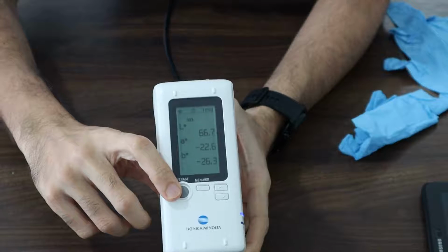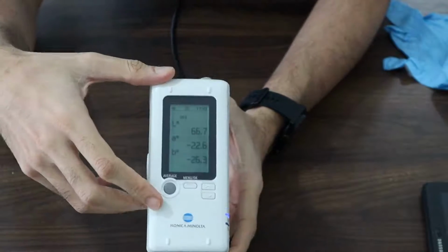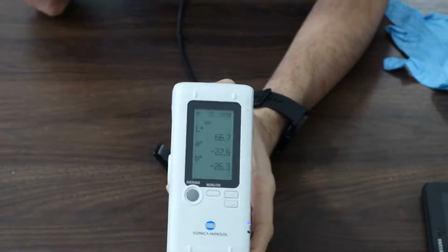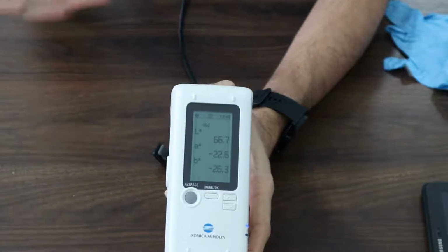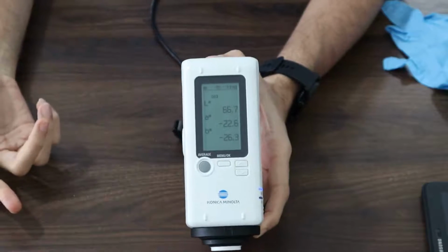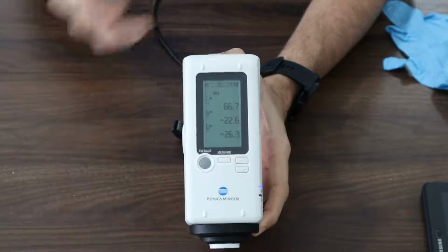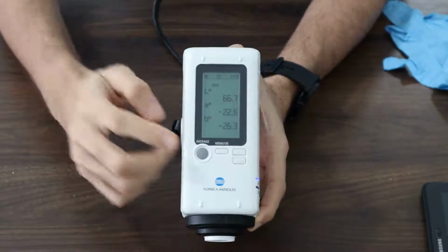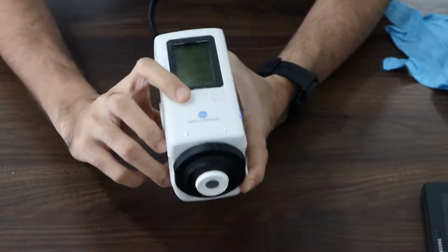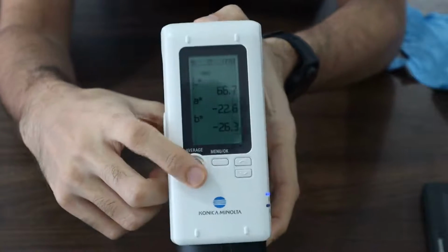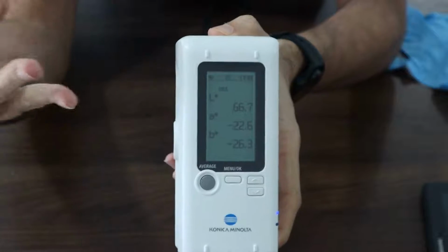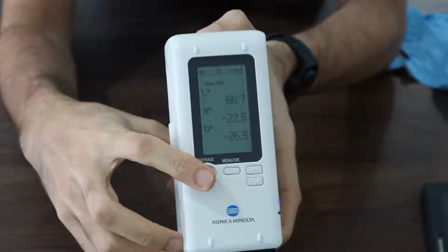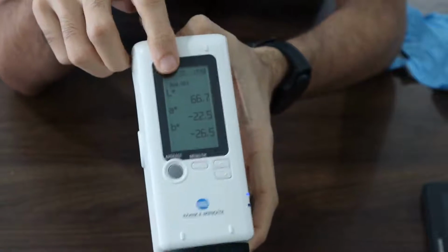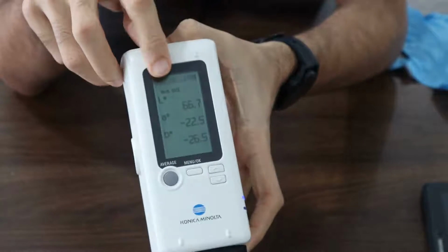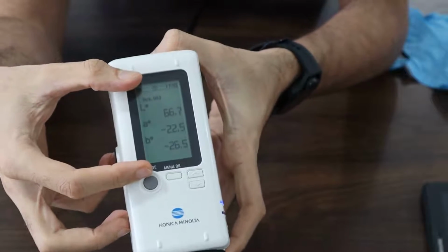This button is an average function button. The purpose of it is that instead of measuring 5 different samples and manually calculating the average, the equipment is able to measure 5 separate measurements, and by pressing average now, currently if you see here it's written 003. So when I click average, it will be the average of the last 3 measurements that I've made. So when I click average, I will get another measurement says AVG 003, and this is the average of 3 measurements.